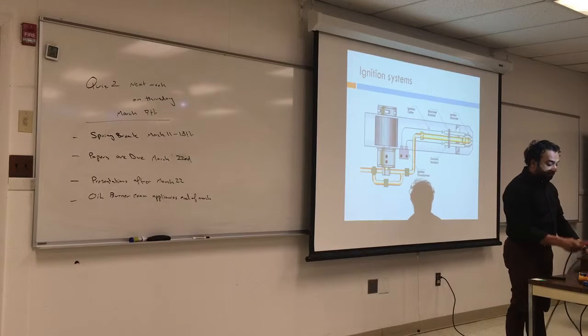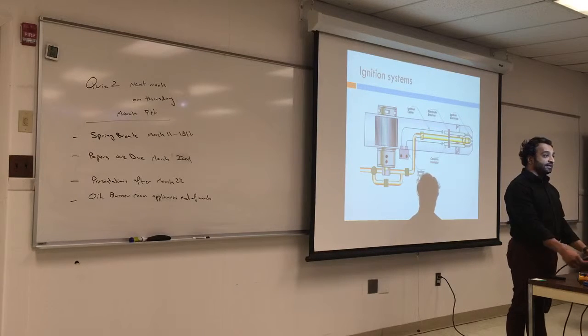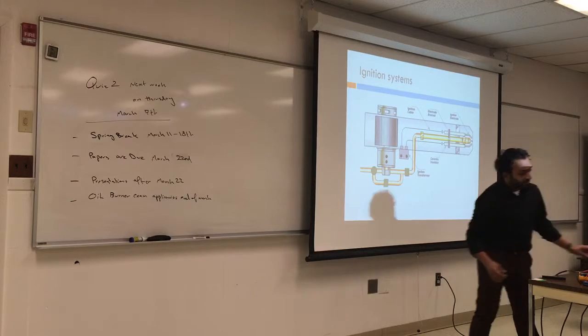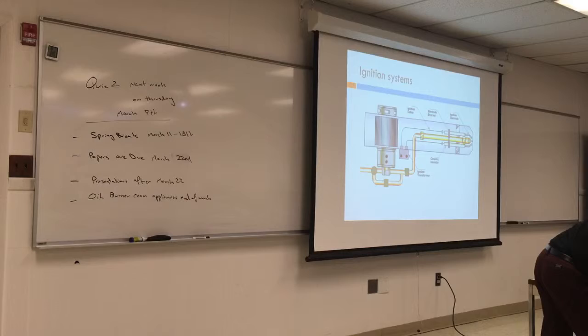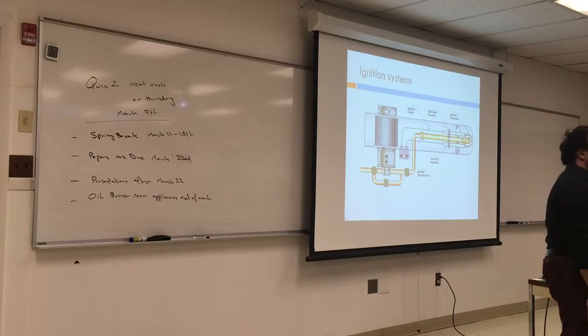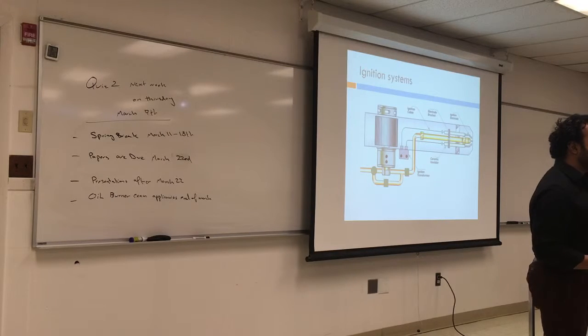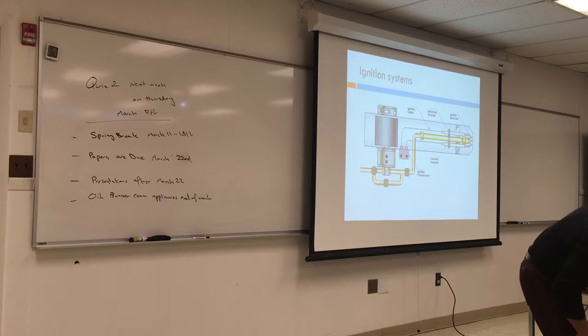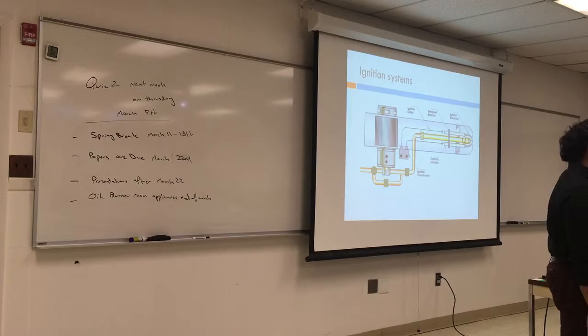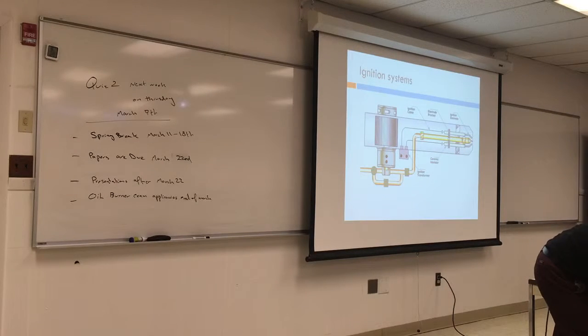So you test your igniter, you plug it by itself, take it out from the control, and it should work. And you can see the ignition here. If you look closely, you'll see a very nice blue spark, 10,000 volts. It's sometimes helpful to take it out of the burner and look at it, because you want to see that it's not touching the plate. What happens if it touches the plate? It's going to arc and it's not going to give you the temperature. So you want to be consistent and very clear.